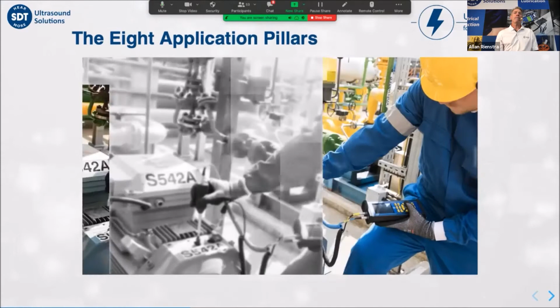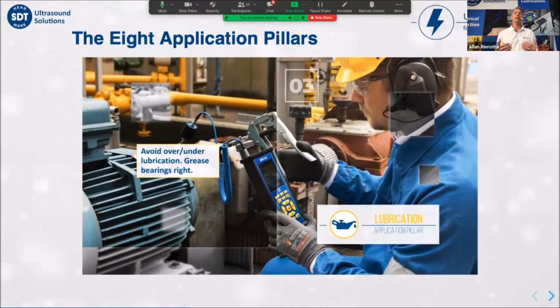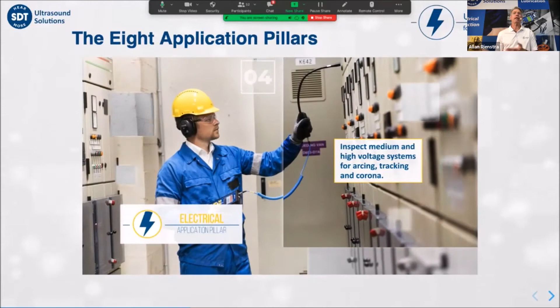Based on this fit principle, we at SDT identified eight primary areas where ultrasound is particularly useful - we call them the eight application pillars. They are: mechanical defects in any mechanical system; leaks, finding pressure and vacuum leaks in high noise conditions; lubrication, using the technology to avoid over and under lubrication of motor bearings, to grease bearings right; electrical - we're going to talk about that today, inspecting medium and high voltage systems for arcing, tracking, and corona; valves, assessing valve tightness and function; and steam systems, finding faulty steam traps and components.